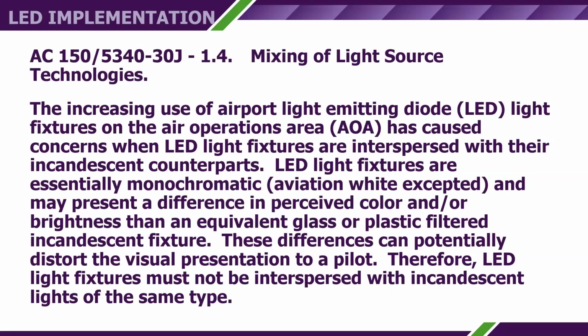Now, those of us who do airfield lighting design on a regular basis refer to the thing as 30J. AC 150/5340-30J talks about mixing of light source technologies. The AC tells us that the increasing use of airport light emitting diode fixtures on the air operations area has caused concerns when LED light fixtures are interspersed with their incandescent counterparts. LED light fixtures are essentially monochromatic, aviation white excepted, and may present a difference in perceived color and/or brightness than an equivalent glass or plastic filtered incandescent fixture. These differences can potentially distort the visual presentation to a pilot. Therefore, LED light fixtures must not be interspersed with incandescent lights of the same type.